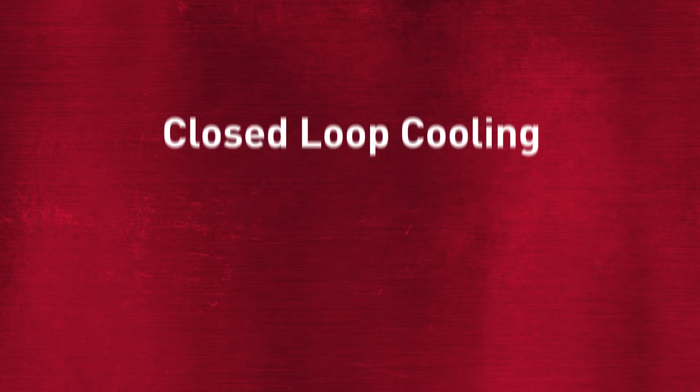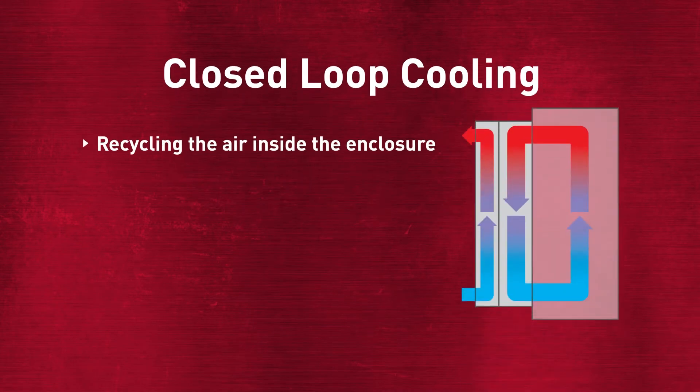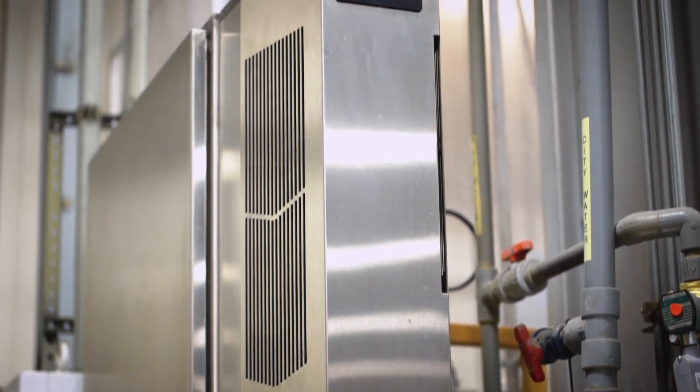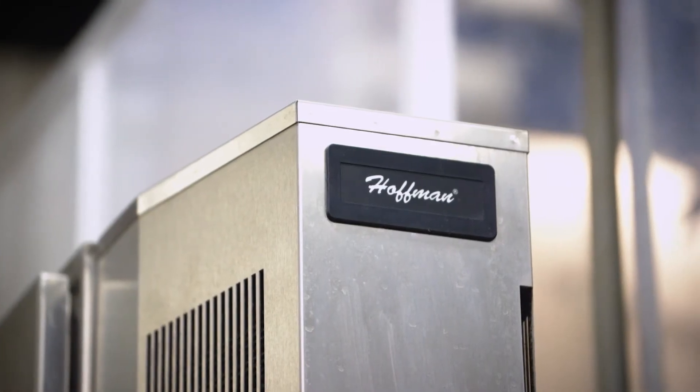In a closed-loop situation, you are recycling the air inside the enclosure. By recycling the air inside the enclosure, that means you're not introducing moist outside air, protecting your equipment from dangerous contaminants and dust. Closed-loop cooling doesn't have to be an air conditioner — it can be a heat exchanger as well. The big thing about closed-loop cooling is maintaining the integrity of the air inside the enclosure.